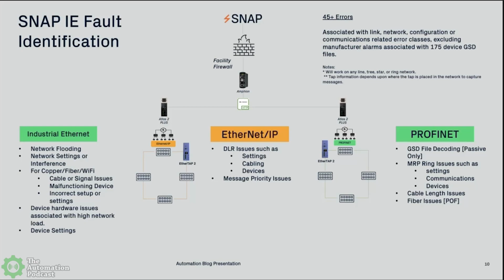For the algorithm, we can identify 45 plus common errors, and we also link to 175 device GSD files. So you can already see that for us, for defining Industry 4.0 human, we're saying here is Industry 4.0, but the field technician is now getting a result using that technology. That result, those 45 plus common errors, helps you more quickly identify what's going on in a network. It helps you solve the problem more quickly, and it really helps guide you through to getting to that root cause. As I mentioned in the 5 steps, we can now apply this concept to the 5 steps.